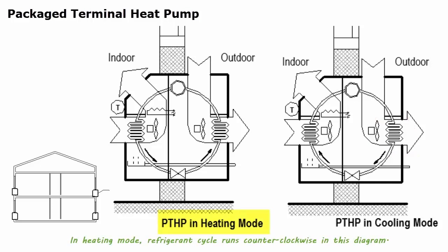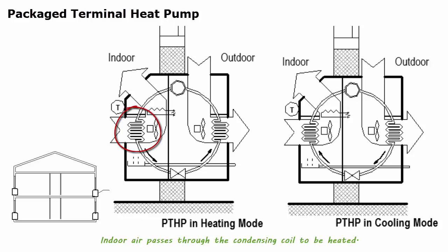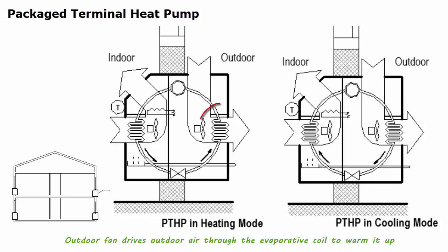In heating mode, the refrigeration cycle runs counterclockwise in this diagram. Indoor air passes through the condensing coil to be heated. Outdoor fan drives outdoor air through the evaporative coil to warm it up when outdoor temperature is not too low.